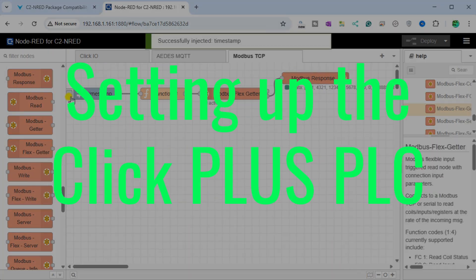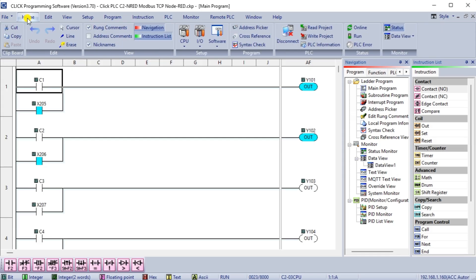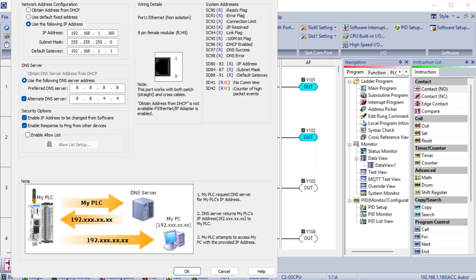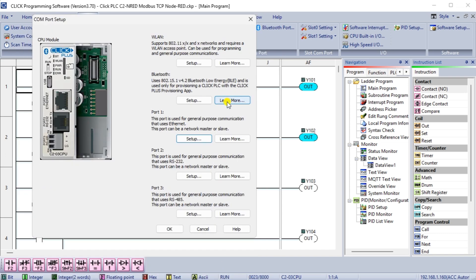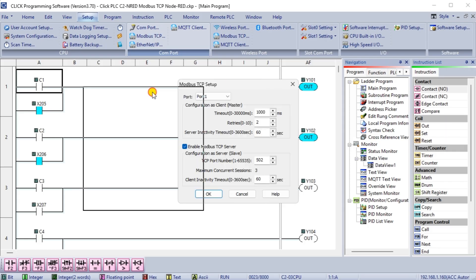Setting up the Click PLUS PLC: returning to our Click PLC programming software, call up the Comport setting window under Main Menu Setup, Comport. Select Port 1 in the Comport Setup window. We will ensure that we configure this Click PLC Ethernet port with a fixed IP address — this will enable our Node-RED flow program to find this PLC on our network. The default for the Modbus TCP server is enabled. In the Click programming software, we will verify this by selecting Modbus TCP from the Main Menu Setup. This is configured with the default port 502.